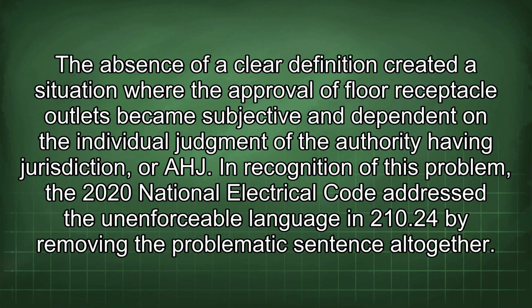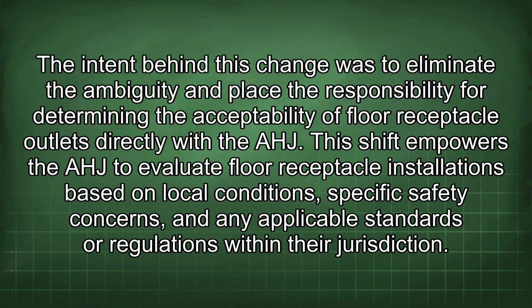In recognition of this problem, the 2020 National Electrical Code addressed the unenforceable language in 210.24 by removing the problematic sentence altogether. The intent behind this change was to eliminate the ambiguity and place the responsibility for determining the acceptability of floor receptacle outlets directly with the AHJ. This shift empowers the AHJ to evaluate floor receptacle installations based on local conditions, specific safety concerns, and any applicable standards or regulations within their jurisdiction.